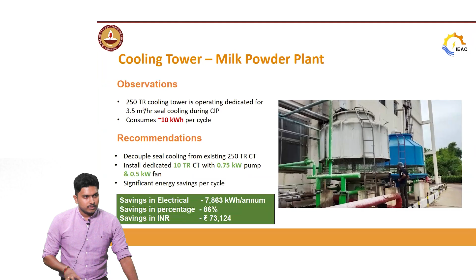A similar principle applies to this two cooling tower setup. In the cooling tower you have a pump used for circulation of water. Usually one pump is for running and the other is for standby, but some people run both pumps. When they are not aware of the situation, they just run both, even though both pumps are not needed to circulate water from the process to the cooling tower.